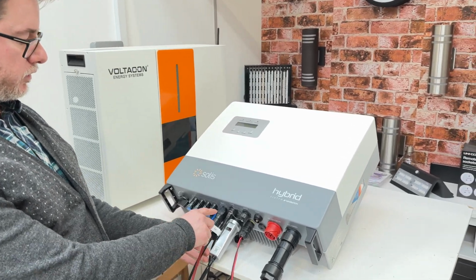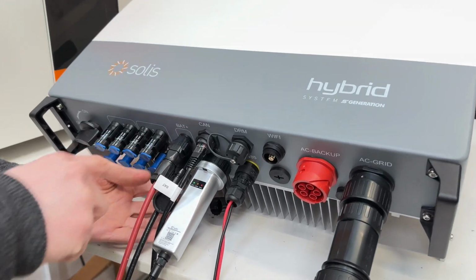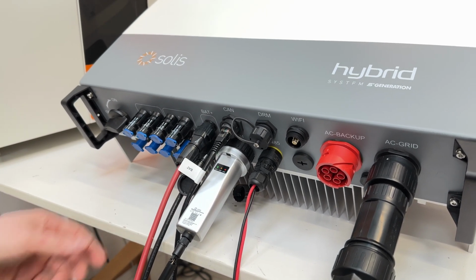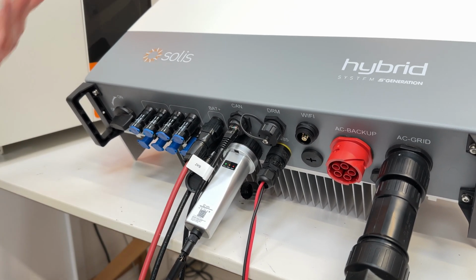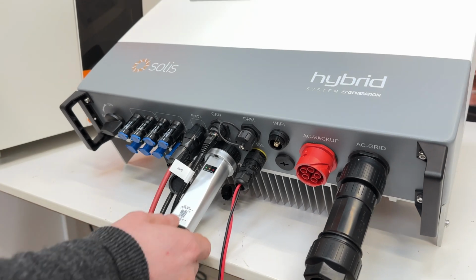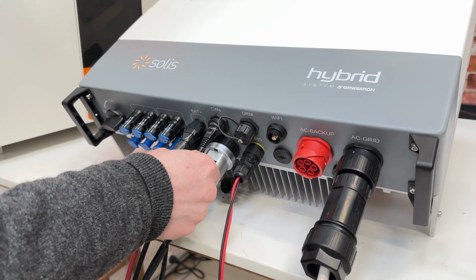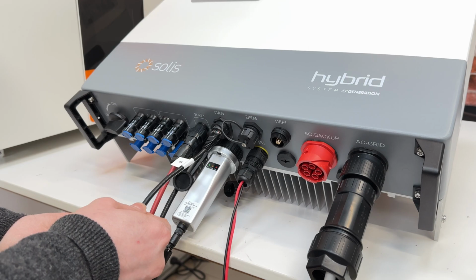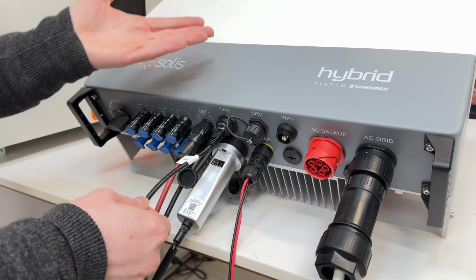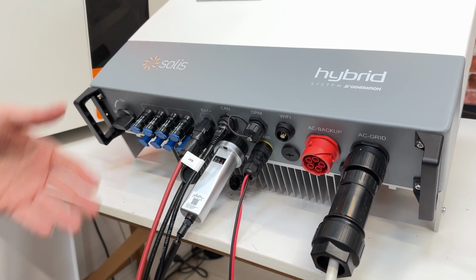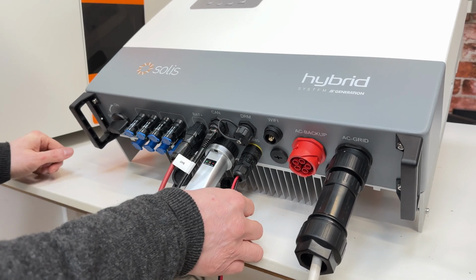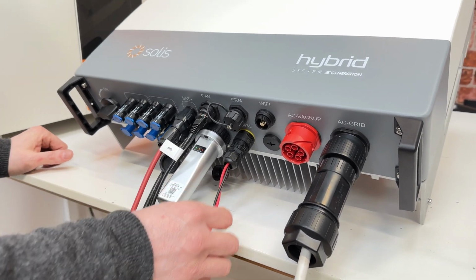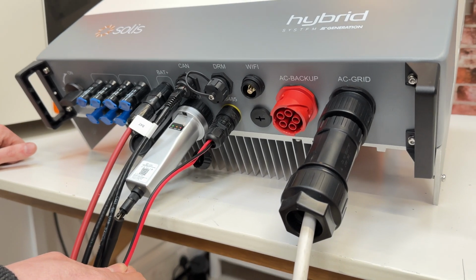We connected firstly the battery. That's the positive and negative connection. Very thin cables because it's a high voltage system. This is our Wi-Fi stick. The BMS cable is a straight Ethernet cable, 8 pins, straight in and out. It's a CAN bus communication. This is the Modbus signal from the energy meter. That's a very important connection.